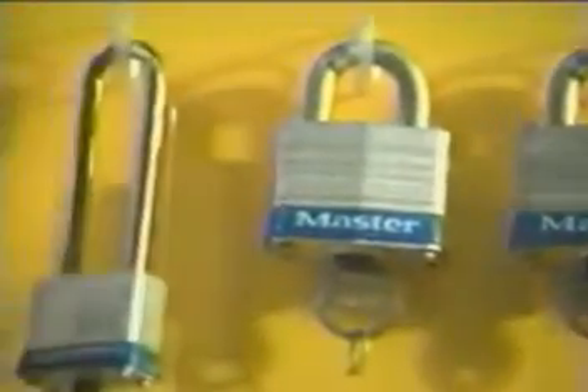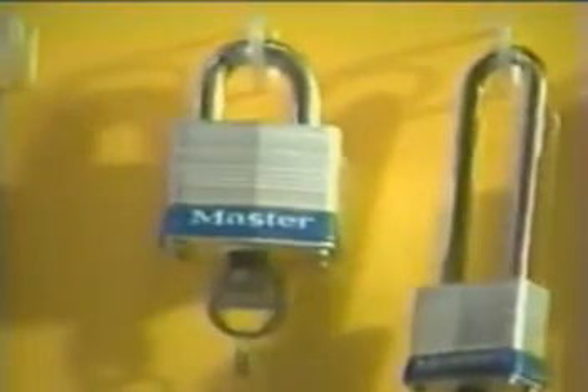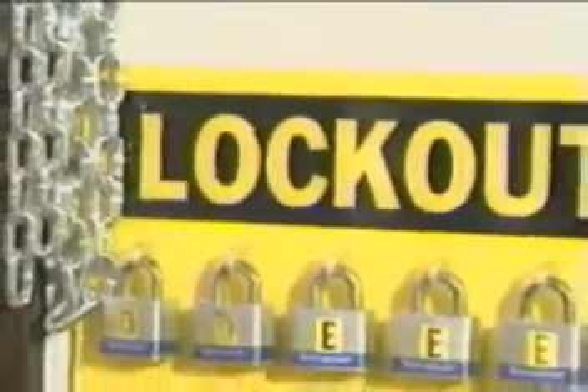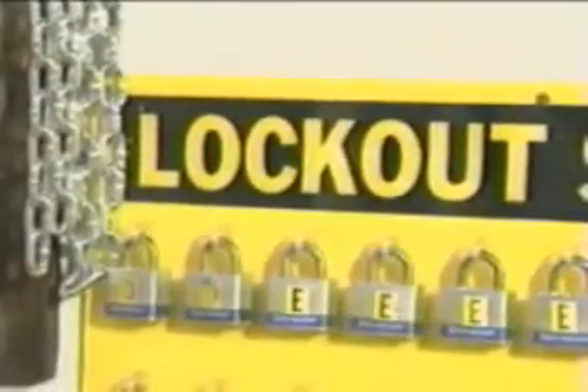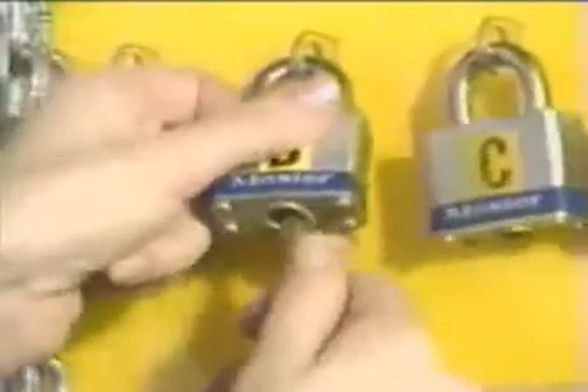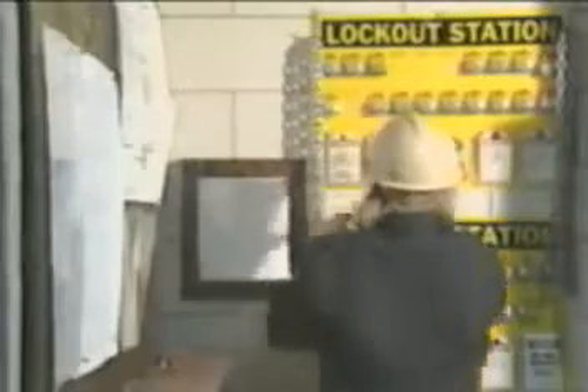Do not use these materials for locking personal items or anything else. Locks and tags are unique for the job, for locking up hazardous energy only. They must be standardized for either color, shape, or size. Your name or clock number or some way of identifying who attached the lock or tag must be listed on the lock or tag itself. You may be given a personal lock to use. Never lend it to a coworker. Make sure you understand the importance and personal responsibility of locks and tags. After all, you literally hold the key to your own safety.